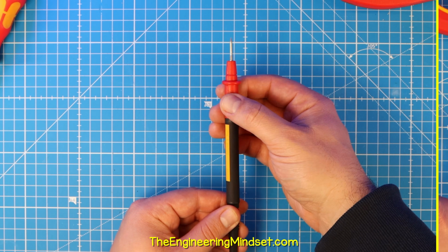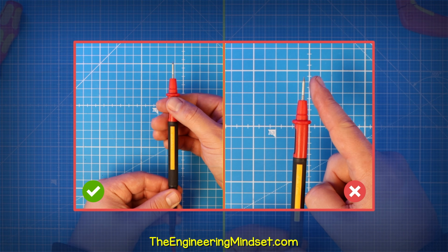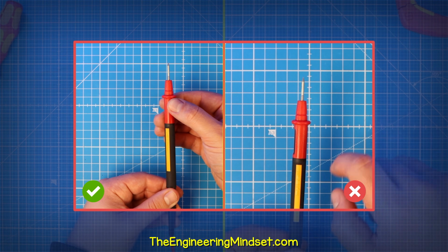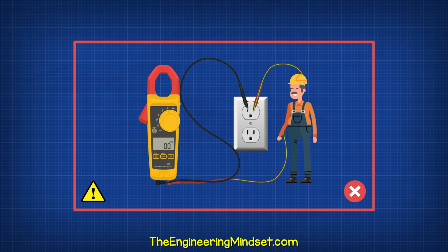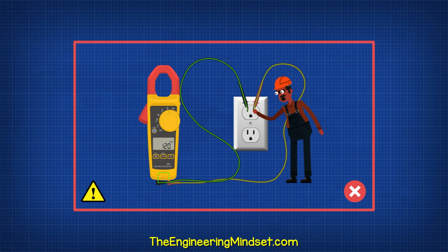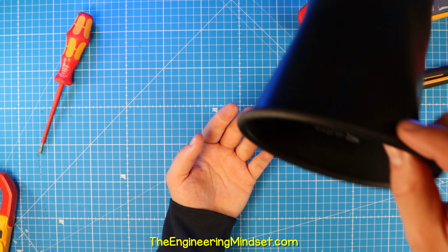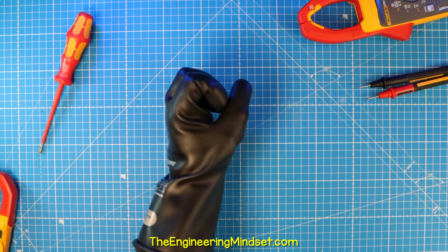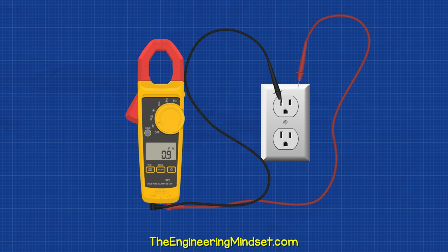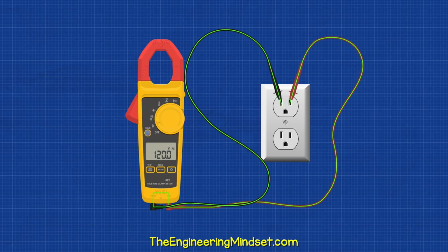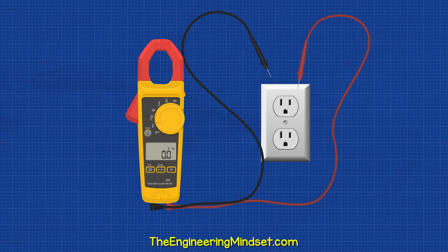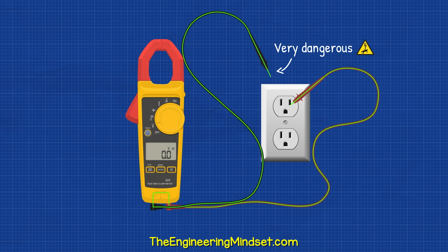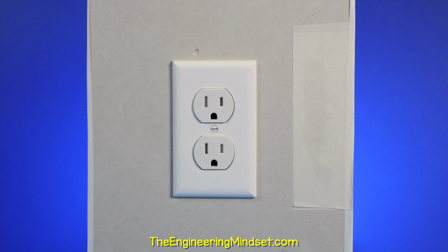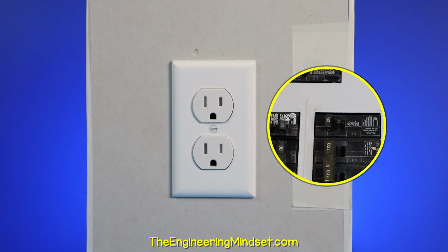Keep your fingers behind the guards on the probes and do not touch the tips, as these will become electrified. If you touch this, electricity can flow through you. Wear appropriately rated electrical safety gloves and protective equipment. Always connect the black wire to the neutral first, because if you connect to the hot side first, the black lead can become electrified. For North American circuits, I recommend turning the breaker off first where possible.